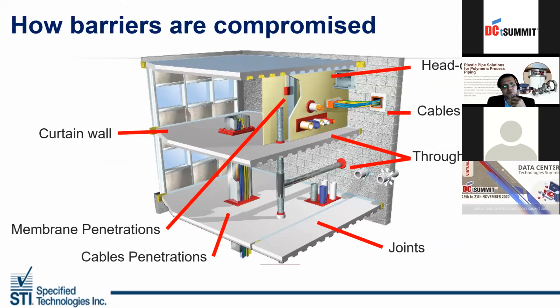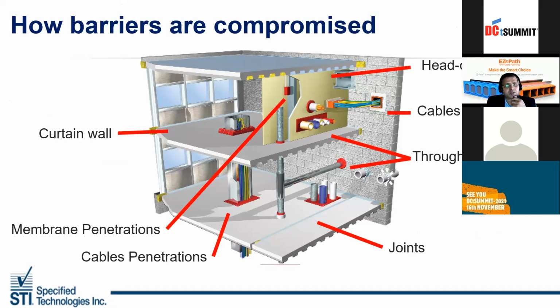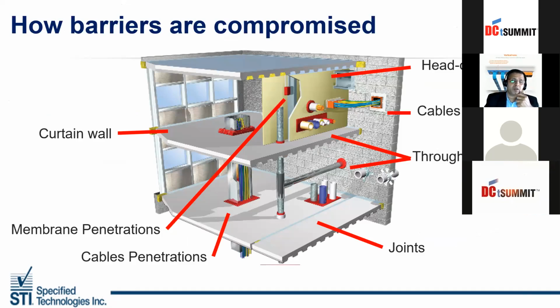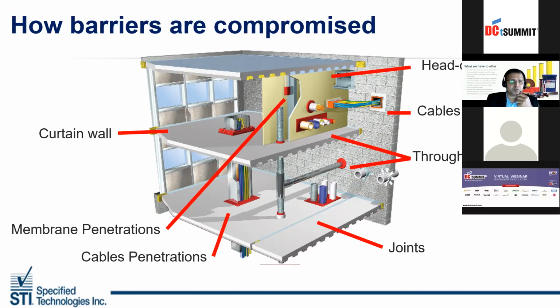Here I'm trying to explain the scenarios in a commercial or residential project where you have a fire barrier to be used. First, to your left-hand side, is the curtain wall. We have membrane penetrations. Those are the areas where it's a fire-rated wall and the penetrants are passing just halfway through. We have systems for those membrane penetrations also. Cable penetrations, where you have cables and cable trays passing through the electrical shafts. Joints, floor to floor or wall to wall, head of the wall joints.